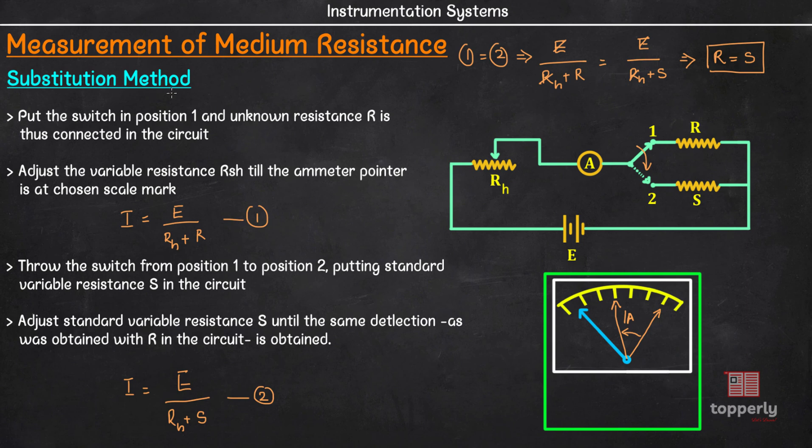Now this substitution method is more accurate than ammeter-voltmeter method. This is because, the ammeter-voltmeter method assumes that the ammeter has zero resistance and voltmeter has infinite resistance. But practically this is not the case. Also there is the problem of lead and contact resistances when it comes to ammeter-voltmeter method. However, all these are not a problem when it comes to the case of substitution method.